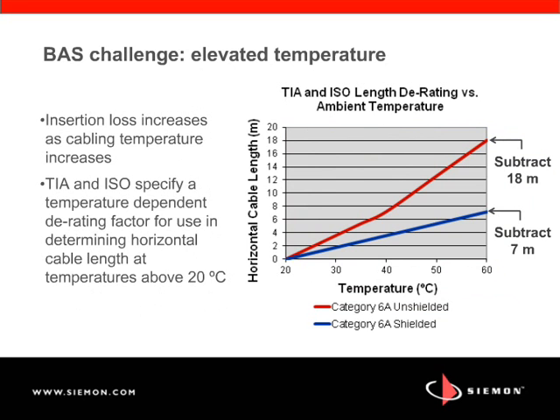Now, many folks are not aware that insertion loss increases as cabling temperature increases, and both TIA and ISO specify a temperature derating factor that reduces the overall horizontal cable length at temperatures just above 20 degrees C. And here in this figure, you can see in red the derating profile for Category 6A unshielded cables. This is length derating, how much I reduce the overall cable length depending on the temperature above 20 degrees C. Now this red curve has a profile that is a 0.4% increase in insertion loss per degree C from 20 degrees C to 40. And then at 40 degrees C, you can see there's a bend. The slope increases to 0.6 from 40 to 60 degrees C.